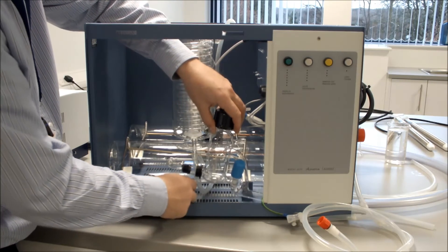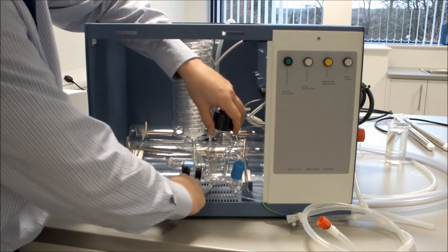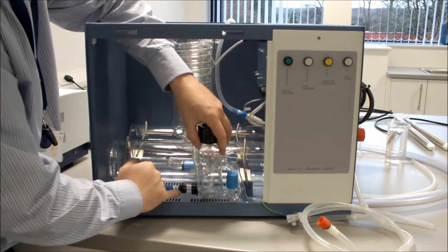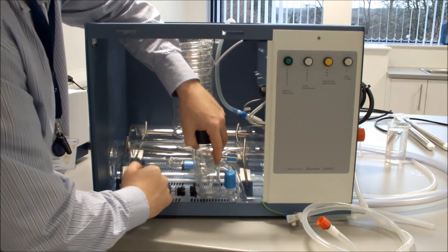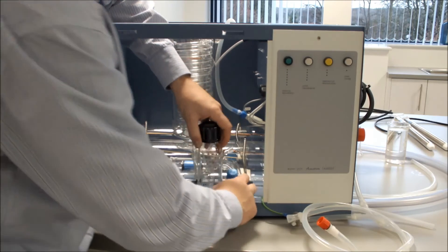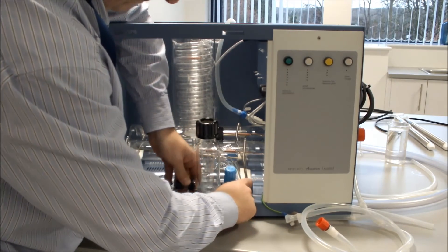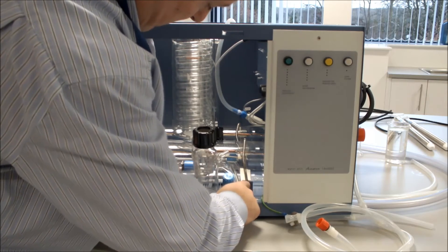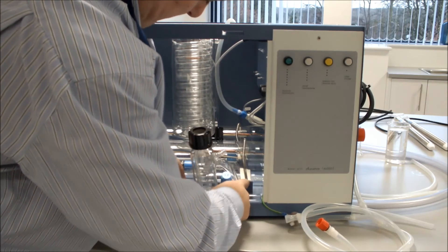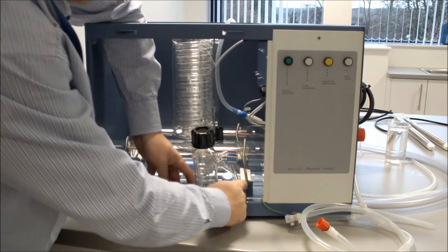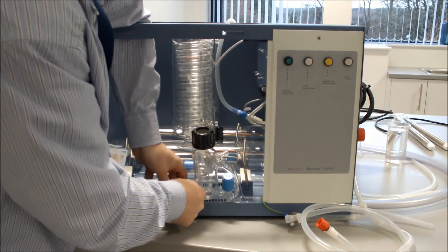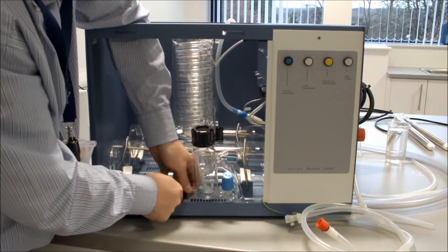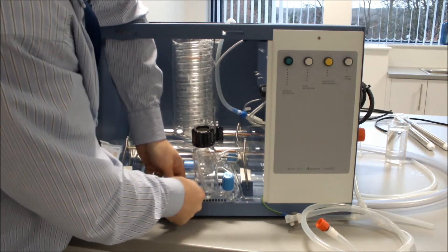We then connect our boiler level control to our boiler. First of all we put the split nut onto the boiler itself and central piece of the connector. The sleeve must fit inside the boiler itself and inside the boiler control. And again our boiler coupling is then done up.